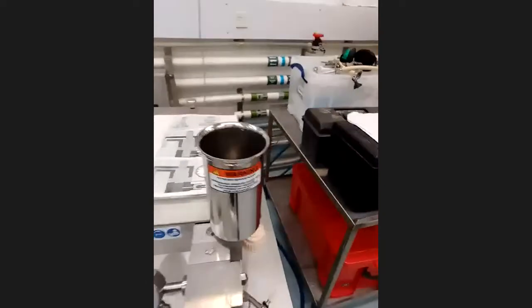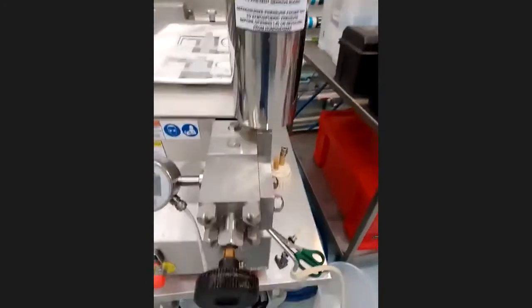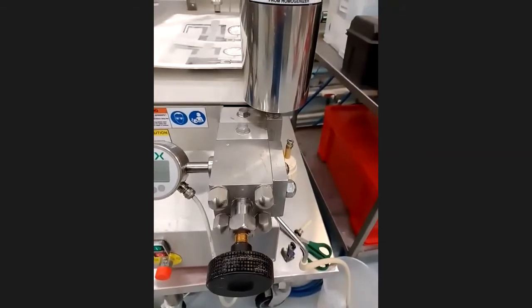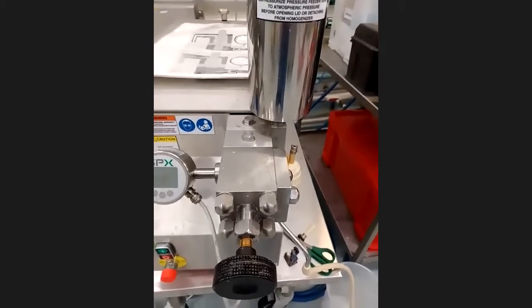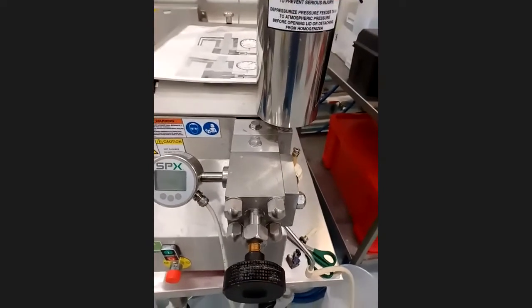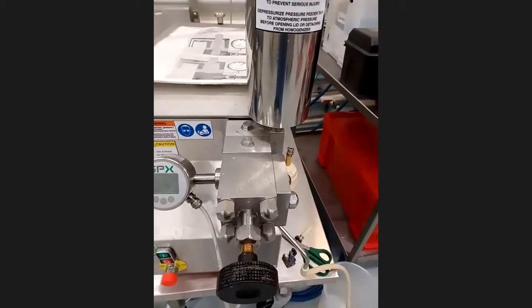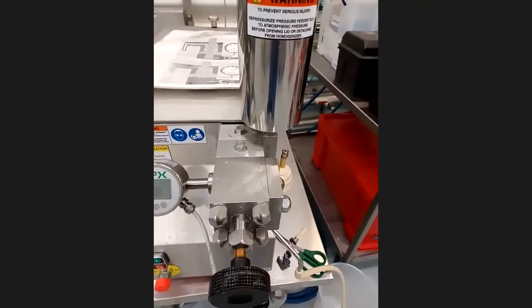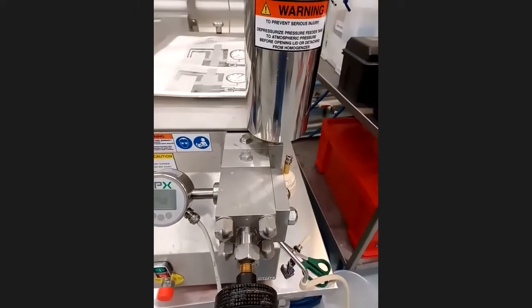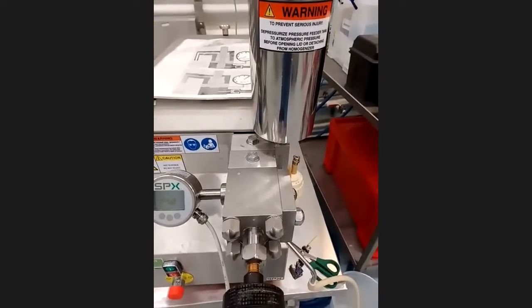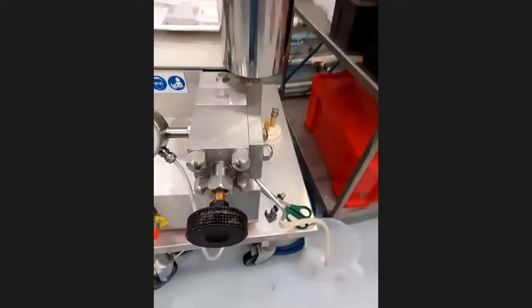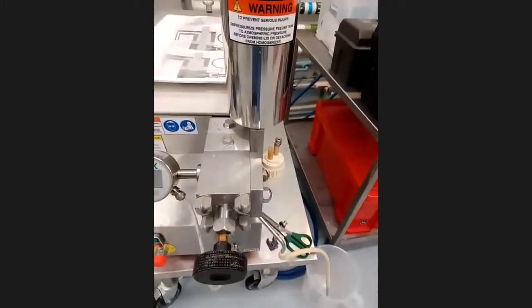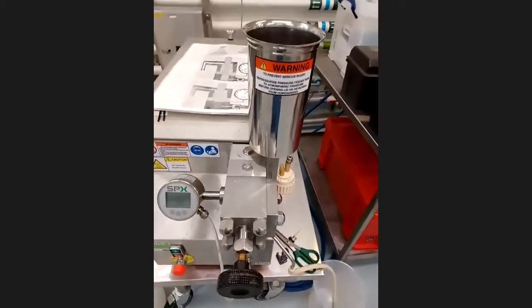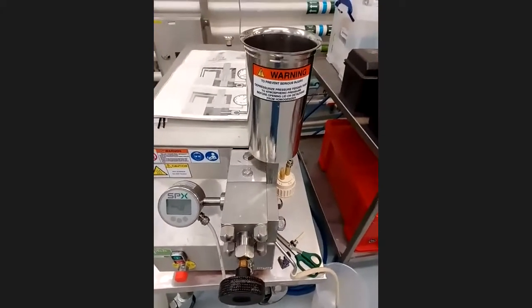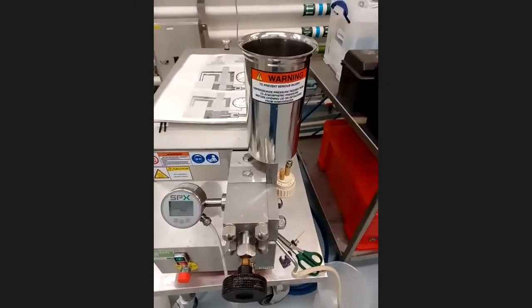We put material into this hopper at the top, okay? Inside this are 3 components. So it goes into this assembly at high pressure. The pressures we're talking about are up to 1,000 bar in this machine, okay? So we go through a small orifice at high pressure, and that high pressure causes the suspension of cells to break open and release their product, okay? So it comes in as full cells and comes out broken open. You might need several passes, but once you've done that, you've released your product into liquid, and what you're left with is cell debris. So that is homogenization.